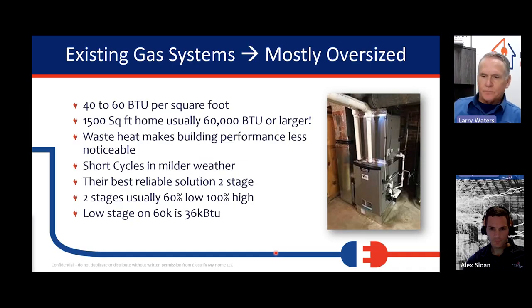So we run into this problem with systems being changed out like for like. A lot of homes that were built in the 70s no longer have the 70s windows. They no longer have trees. They have a little better insulation maybe, or the customers have remodeled some things and made it tighter, or whatever. But most houses from the 70s aren't existing the way they were when that system was installed in the 70s. So for us to take out a system that was installed in the 90s because it replaced the exact size of the system from the 70s, and put the same size system in now in the 2020s, that's not good business practice. It's not good electrification for sure, and it's not something we should be doing with heat pumps.